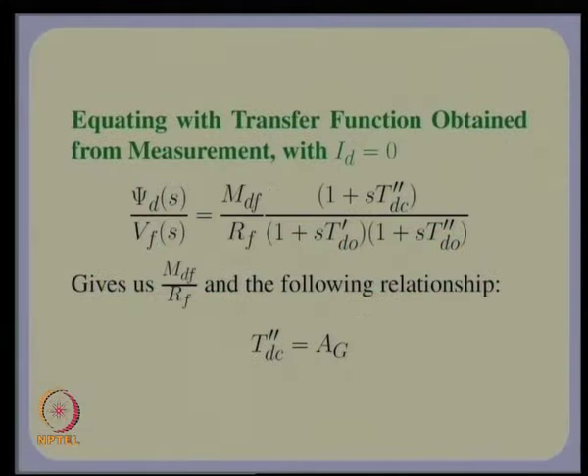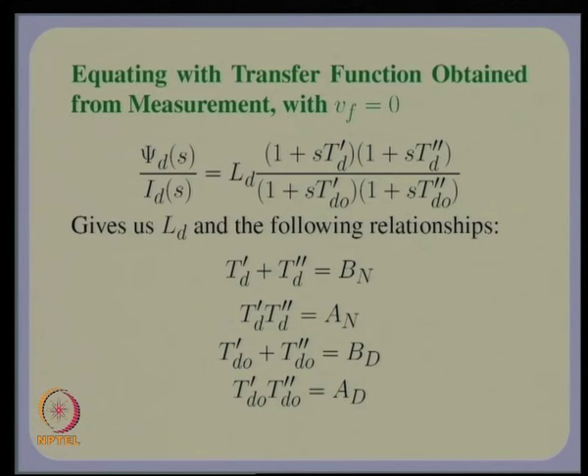The basic idea is to back-calculate the basic parameters from the measured standard parameters so we can use our model in realistic studies. However, if we use only one measurement, we have a problem: the number of basic parameters exceeds the parameters obtained from measurements. What we obtain from measurement are simply L_d, T_d', T_d'', T_d0', and T_d0''.